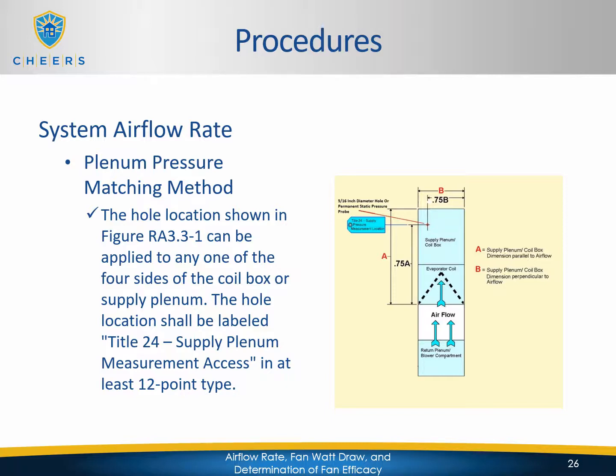issues, it is okay not to have the holes drilled for the HERS rater, you, basically to see that they're not drilled, but it has to be verified by you to make sure that there is an actual reason why those holes were not drilled. If the plenum is accessible and the holes are not drilled, that is going to be a failure on our part. So even if the system passes the adequate airflow and fan watt draw, but yet the holes are not drilled, the system will be a fail. So keep in mind that exception when it comes to those access holes in the plenum.